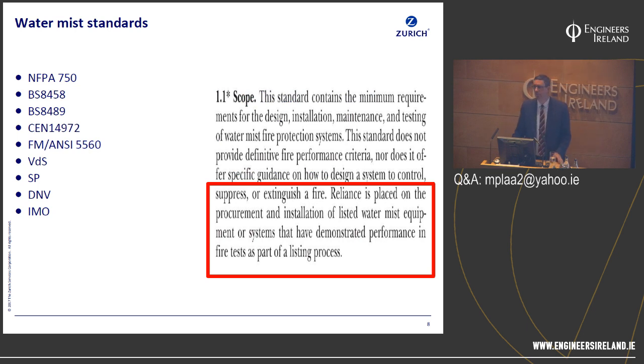Now, there's a list of standards on the board there, and it's common for us to receive design or specifications with a list of standards. Well, which one matters? Well, they all matter in their own way, but the most important thing to remember is NFPA 750. Have a look at 1.1 and have a look at the red box. Because you don't have to read NFPA 750. The most important part of that is the scope and reliance placed on listed water mist equipment and demonstrate performance in fire testing as part of a listing process.